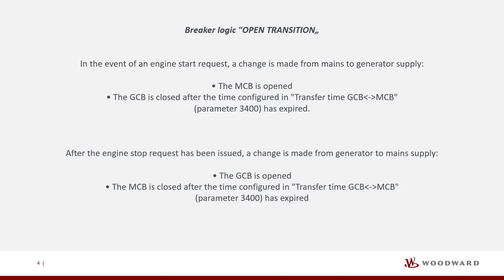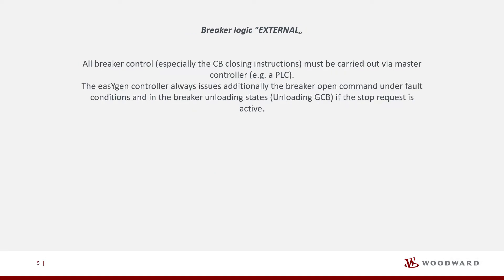Breaker logic open transition: in the event of an engine start request, a change is made from mains to generator supply. The MCB is opened. The GCB is closed after the time configured in transfer time GCB-MCB, parameter 3400, has expired. After the engine stop request has been issued, a change is made from generator to mains supply. The GCB is opened. The MCB is closed after the time configured in transfer time GCB-MCB, parameter 3400, has expired.